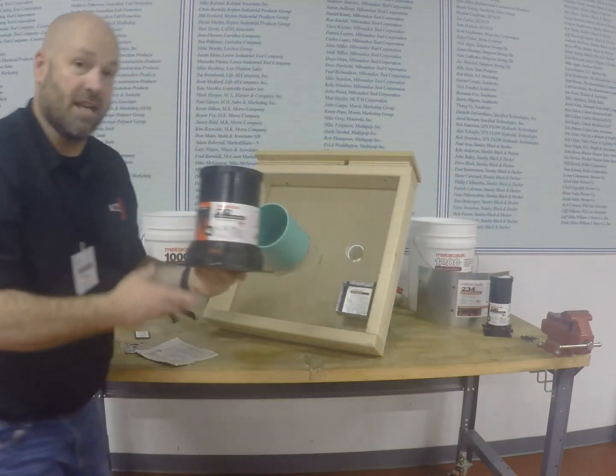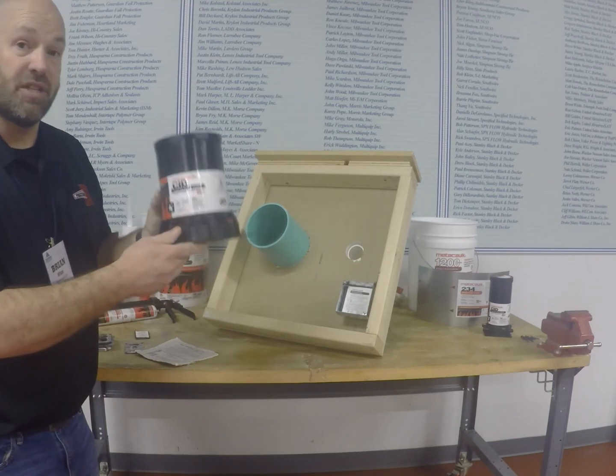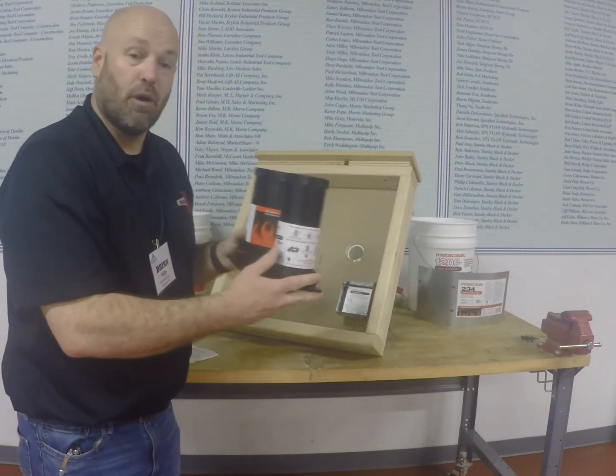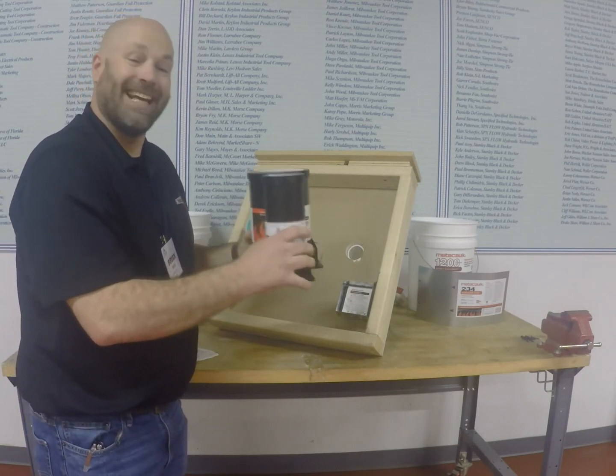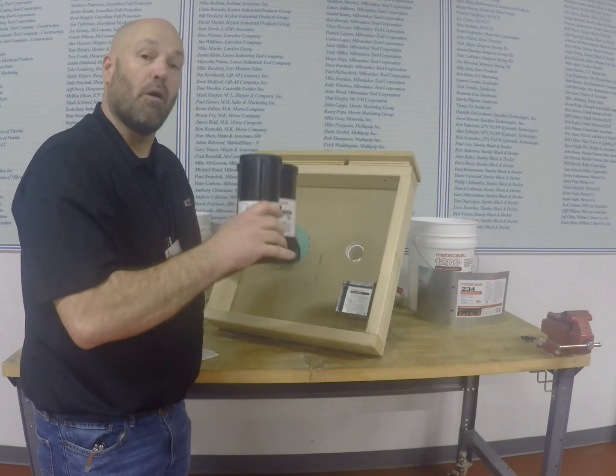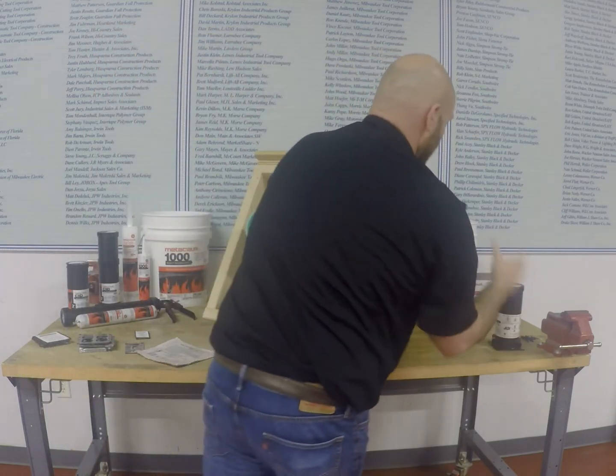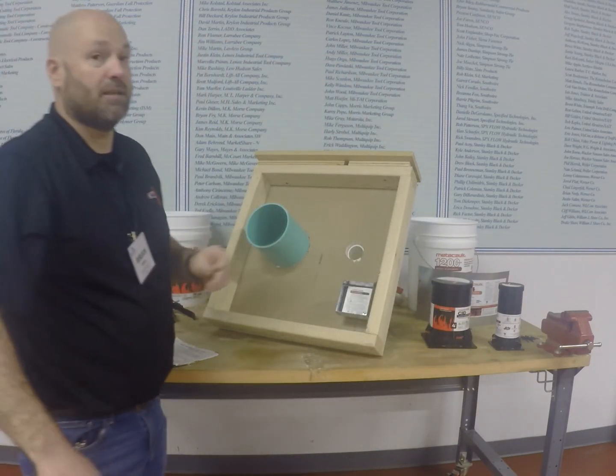We also have our new cast-in-place devices. Those range from two, three, four, and six inch. It's a very simplified, very sturdy product — eight inches high — that allows you to connect multiple together, securing them on the floor before the concrete is poured. Good for both metal and plastic, all in one, making install easy and allowing transition from plastic to metal pipe.